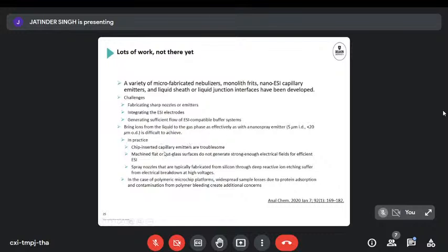In practice, a lot of the electrosprays are developed for capillary chromatography or for capillary electrophoresis. The easy thing to do would be to just use those interfaces and stick them into a chip. In reality, sticking a fused silica capillary into a chip is really hard, because typically we make our channels accessible from the top, not from the sides, and fused silica capillaries have the problem that they're round. Nothing is more difficult than creating a circular channel. We've seen a lot of squares in all my slides. We had the glass where we had the underetching, so we had a little bit of a rounded cup. I bet you haven't seen a lot of circles in my slides. Very hard to get a round peg into a square hole. So it's not easy to use the technology that's already been developed for capillary electrophoresis to just physically connect that with a microchip.